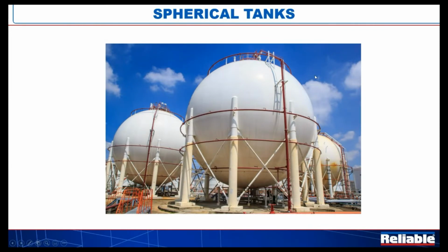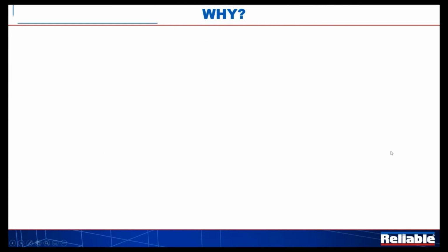Again, here with the spherical tank, you can see that we have rings of protection, and you'll notice that at about the equator of that tank, the rings of protection become closer together. Obviously, that's because we don't have rundown past the equator, and we'll talk a little bit more about that. But again, here's a pipe routing, curved bent pipe supported on the stanchions of the tank. So again, just an opportunity to be creative. We're not going to get into the details of the systems in terms of their operation. Just think in terms of deluge systems, right? Electrically actuated, wet pilot, dry pilot, open nozzles typically. So we're not going to get into those details. That's a presentation that we've either had or we can do in the future.